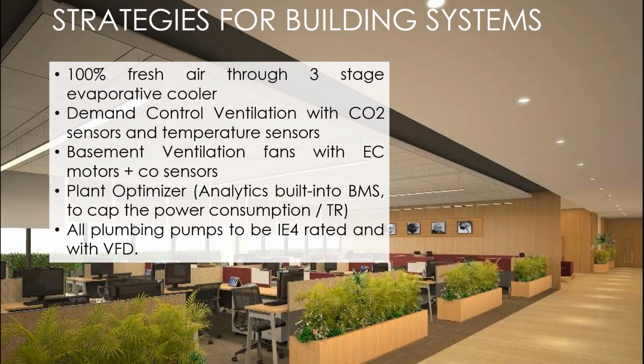Then when you come further down, we have taken all pumps to be IE4 rated. Even if you go out today in the market, you would find that IE4 rated is not easily available and they are a long lead item. But three years back, we convinced the client that, sir, even though there is a long lead, these products are available, and let's go for the most efficient pumping system available in the market. So my pumps, my motors for air handling units, ventilation fans, heat recovery, everything is IE4 rated.